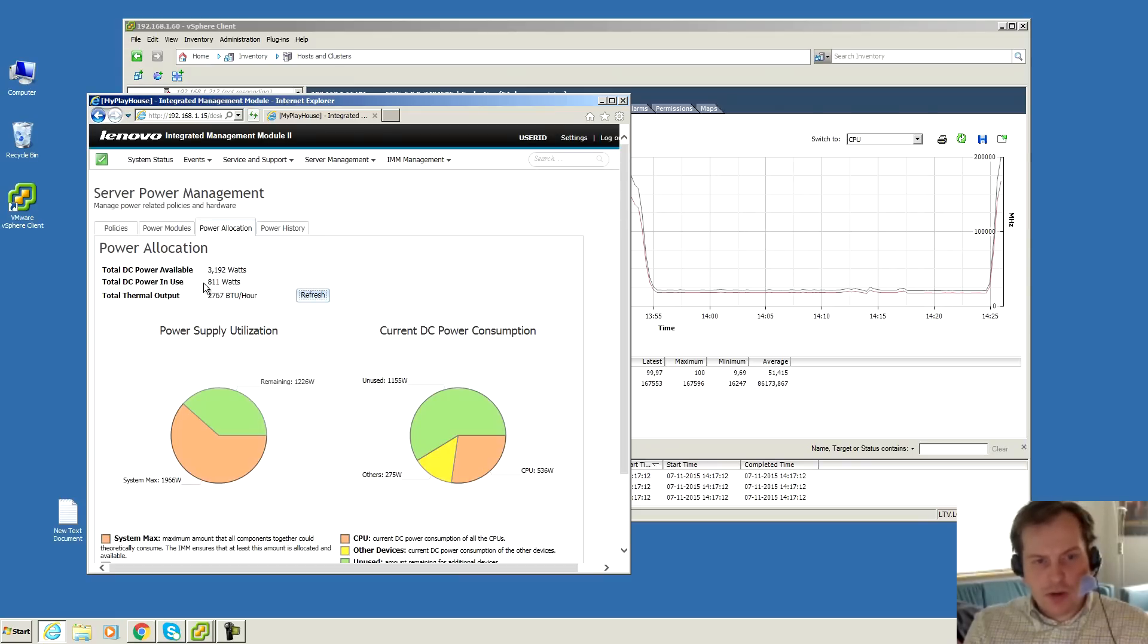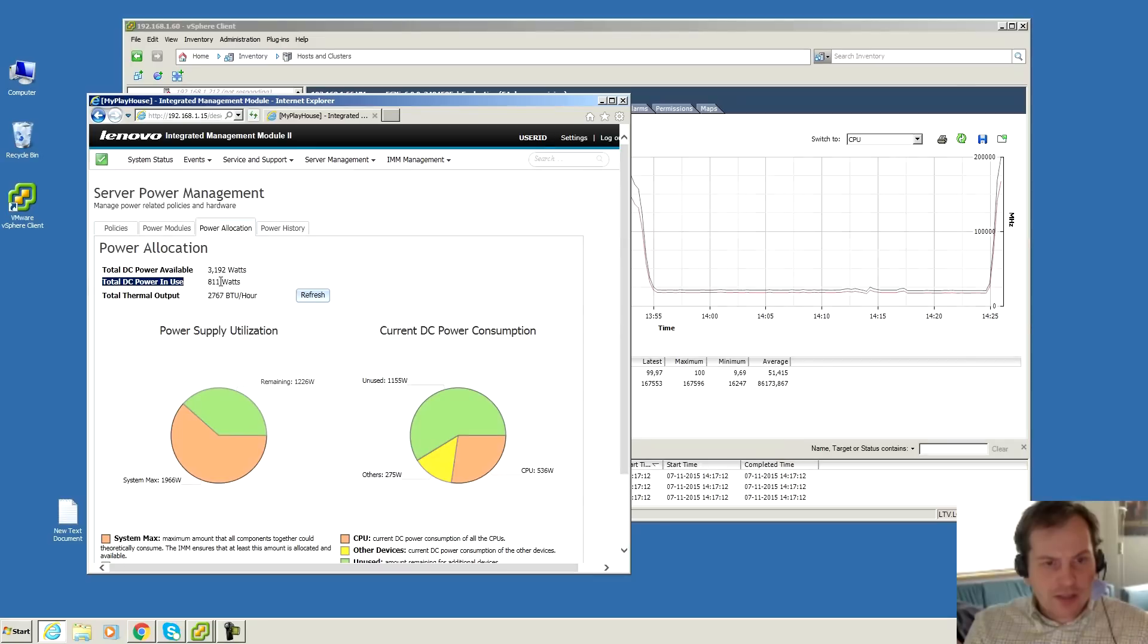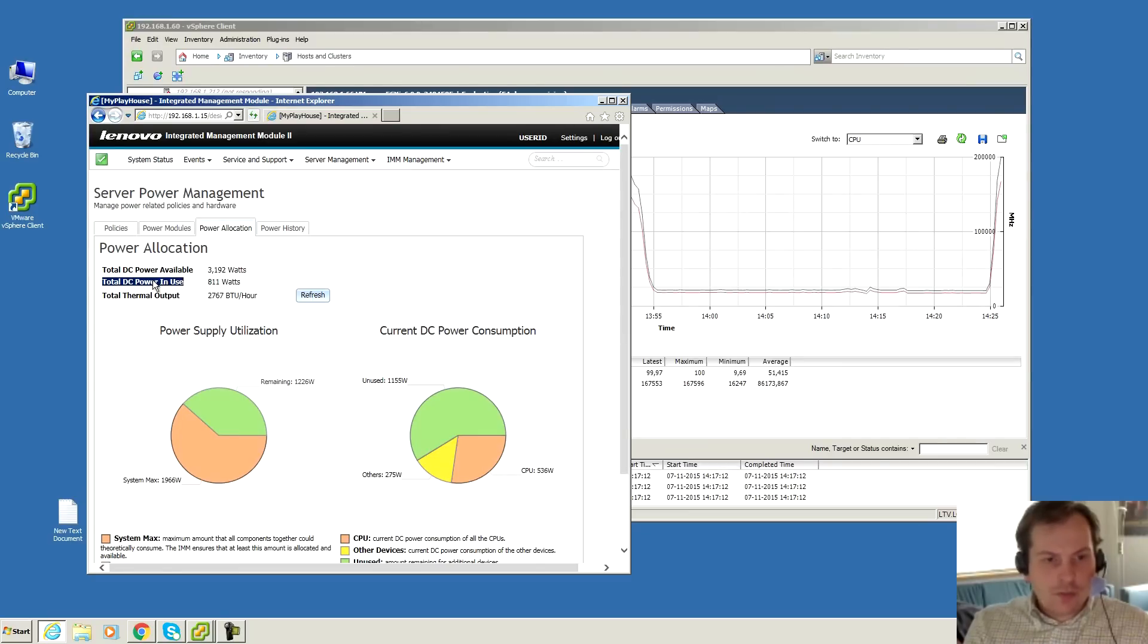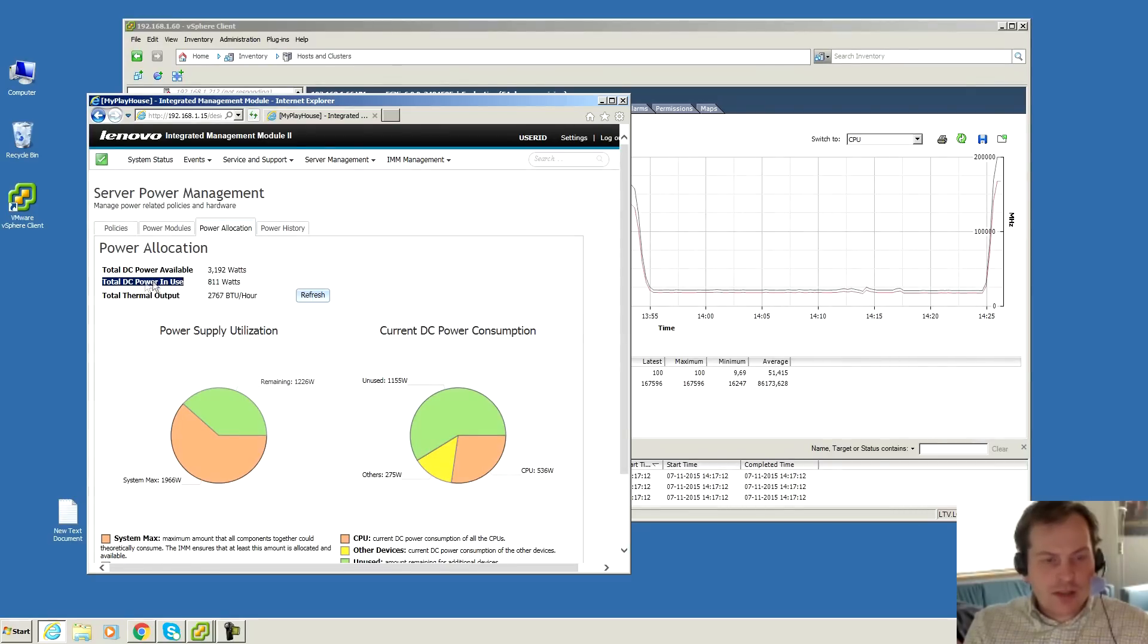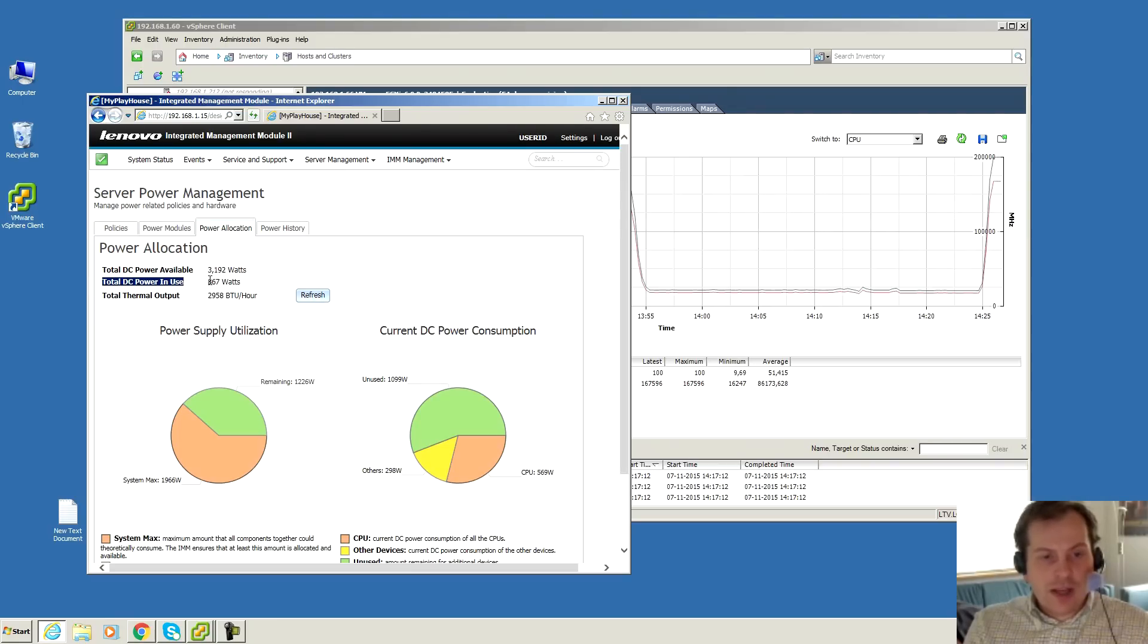Each of the power supplies are 1400 watts. This is the DC power in usage. So it's using 811 watts DC power. The power supplies convert from AC to DC and there are some losses there too. If a power supply is like 80% efficient, that means that if a power supply is doing like 1000 watts AC, you would only get 800 watts DC of usable power.